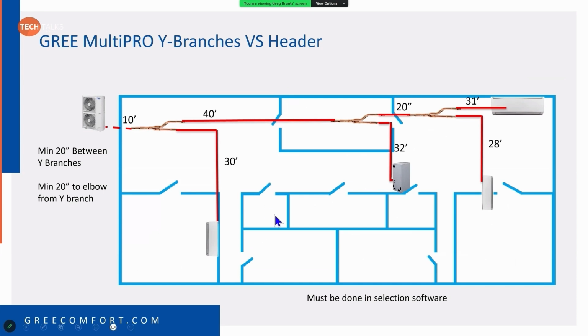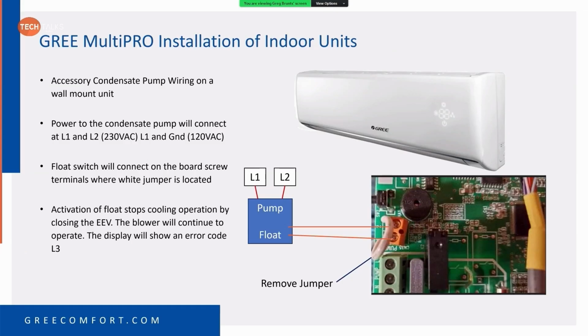Some more information about installation of these units, just an FYI. If you do put a condensate pump on a wall mount, the wall mount does have a place to connect the float. If you look at this picture closely, it says pump down here. That doesn't work properly. So what I tell guys to do is take your pump power, go directly to L1 and L2 on your terminal block, and then take your float, take this jumper off, undo those 2 screws, take the jumper out, and hook your float on those 2. If the float opens on the condensate pump, you will get an L3 error code.